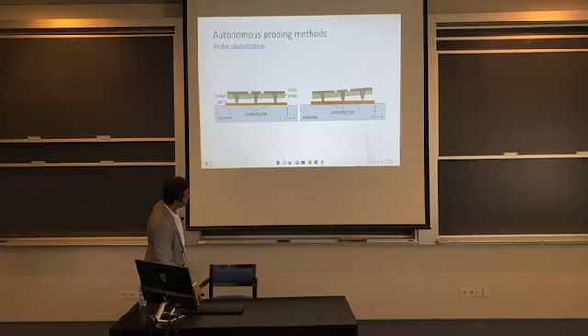Now how do we ensure that? We use basically an image processing algorithm where we actually detect the intensity of scratch marks. So each of these pins leaves a certain marking on the substrate. That's why these measures are called destructive measurements, because every connection that we make changes the behavior of the device. And so we make a contact, a series of contacts, during which we change the planarity, so the angle of the probe. And using this algorithm, we were actually quite successful in planarizing the probe within a certain region.